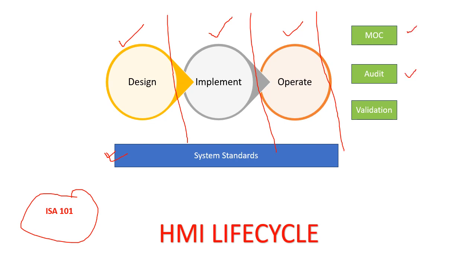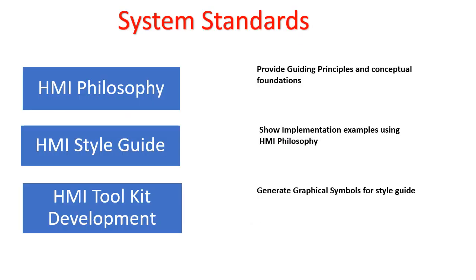Across all three lifecycle phases, there are three things that are common: MOC, audit, and validation. These three things can come anytime between these lifecycle phases. System standards as per ISA 101 consist of three different things: one is HMI philosophy, another is HMI style guide, and the third is HMI toolkit development. HMI philosophy provides guiding principles and conceptual foundations, HMI style guide provides implementation examples with respect to the HMI philosophy, and toolkit development involves generating graphical symbols for the style guide.